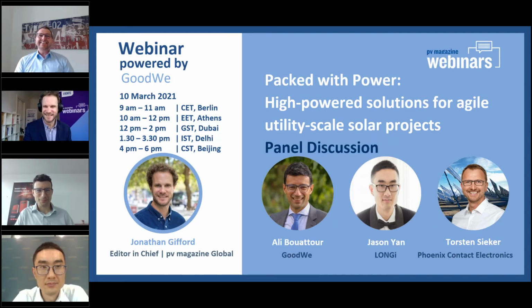Without regulations, you simply follow active power control based on the grid frequency. Aligned with the grid operator, you can set the frequency set points and the ramping, how fast the control should react. That's agreed between the grid operator and the EPC. The tricky part is that without regulations you have to do this one by one, but the control technology in the background can handle different set points.